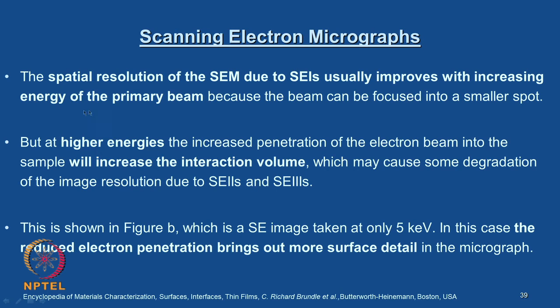To summarize: the spatial resolution of the SEM due to SE1 usually improves with increasing energy of the primary beam because the beam can be focused into a smaller spot. But at higher energies, the increased penetration of the electron beam into the sample increases the interaction volume, which may cause degradation of image resolution due to SE2s and SE3s. Image B, a secondary electron image taken at only 5 keV, shows that reduced electron penetration brings out more surface detail.